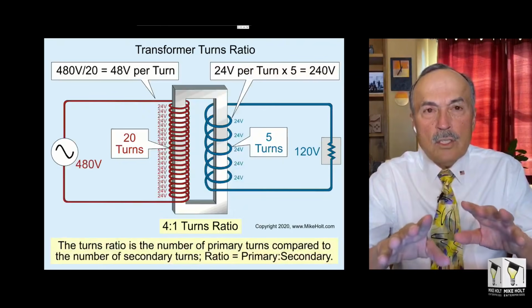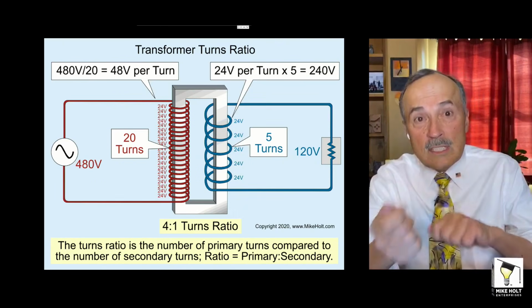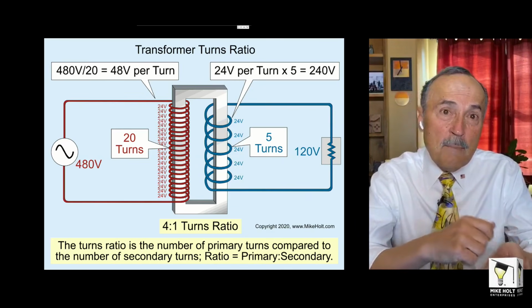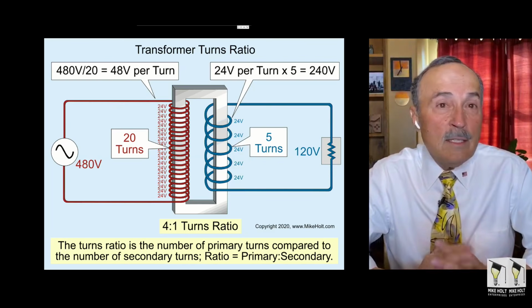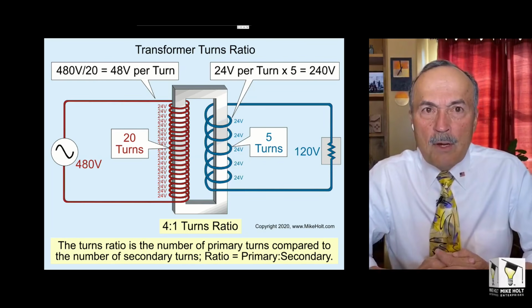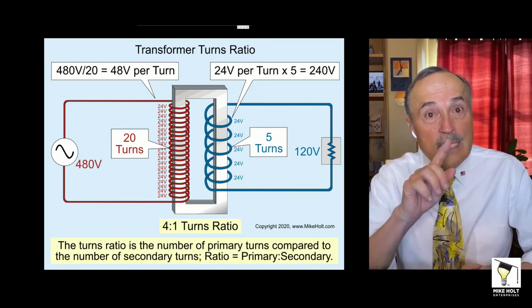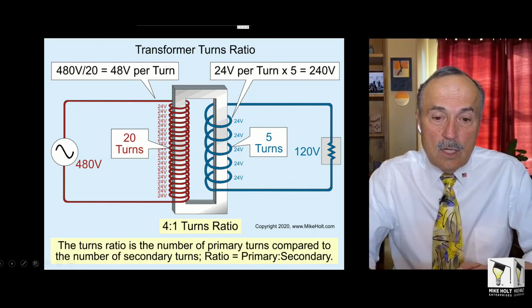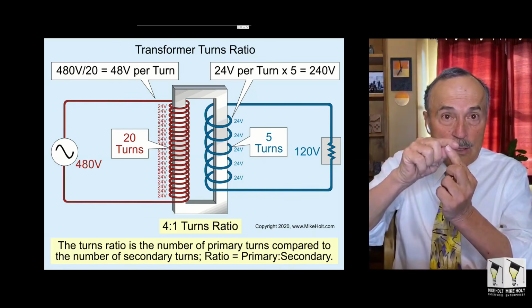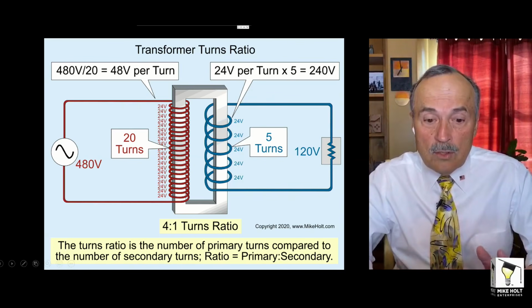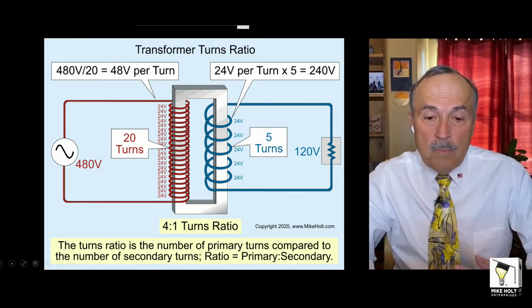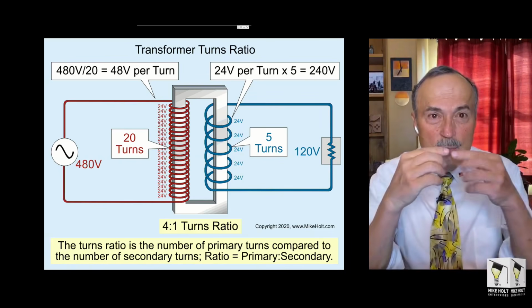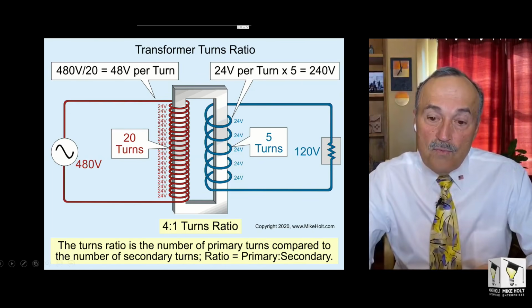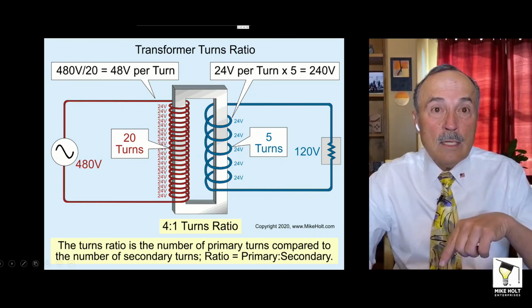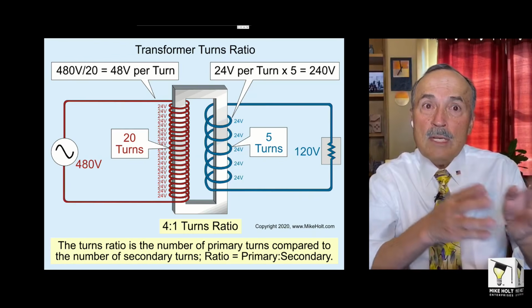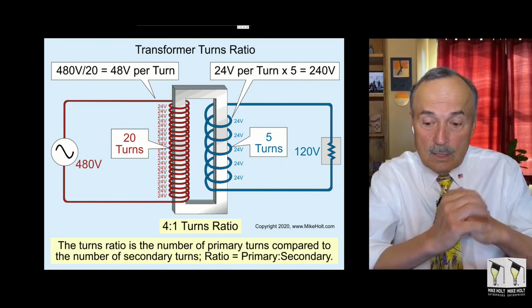Okay, now there's a turns ratio. The number of turns on the primary relative to the number of turns on the secondary is how we're able to get the different voltages to step it up, to step it down. An example right here is showing you, let's say, just using relationships here. Let's say there were 20 turns in the primary, and the voltage of the primary is 480. What that means is that each individual winding turn is going to be 24 volts. In other words, that's the effect of that section. And then on the secondary, let's just say there were 5 turns, so the ratio is going to be what? 4-to-1 ratio. But each winding is still going to be 24 volts on the secondary because they're really pretty close to each other, okay? So now if you have 5 turns on the secondary at 24 volts, then you're going to get 120. Again, it's not that big of a deal, but there is a relation between the primary and the secondary voltage, and it's that ratio that gives us the different voltages to step it up or to step it down.